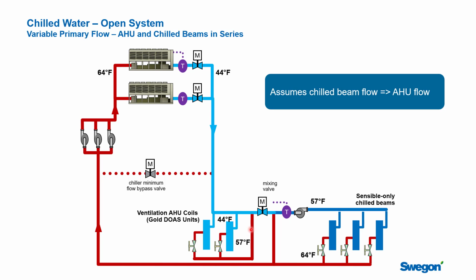The second thing is, if we were talking about a fan coil system and the ventilation unit for it, roughly speaking, the ventilation is going to be 20% of your building load. Now that, of course, changes a lot depending on whether you're talking about a K-12 school or an office building, which have very different ventilation load requirements. But whatever it is, the ventilation load is going to be noticeably smaller than the internal heat gains in the space. That is not true when it comes to chilled beams, for a couple of reasons.